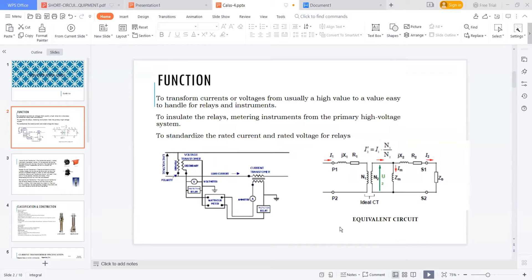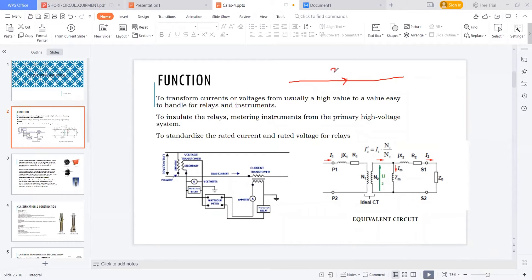First, I will explain some basic understanding of the current transformer and potential transformer. As we discussed, recall our project — a 200 megawatt wind power plant. We are having 33 kV feeders, and as discussed in earlier classes, each 33 kV feeder from the wind farm is generating 20 megawatt of power at 33 kV voltage level. If you find the current here, it comes to nearly 400 amps — let's assume 400 amps.